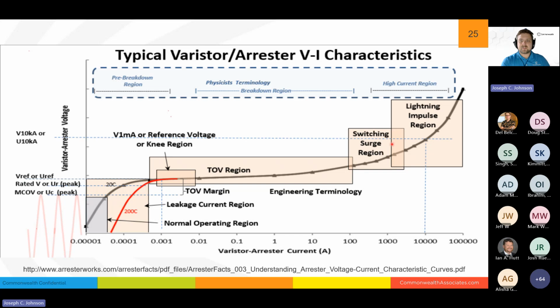Once you get into your switching surge region, they're still lower than lightning impulse, but they last a lot longer. So imagine an impulse that's only 1/10 of the current, but potentially 20 times as long. It'll carry a lot more energy. And then we get up into lightning impulse region, where we actually start to see the behavior start to fall off and be a little bit more voltage dependent on the current increase.